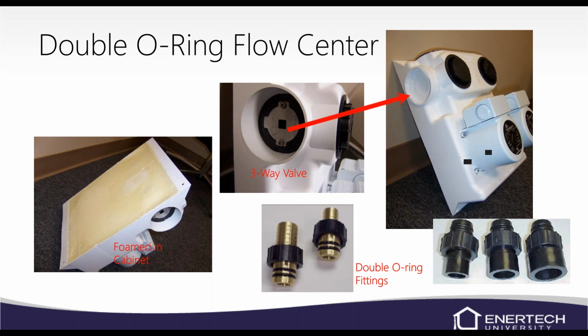And I just say, be real careful and double check to make sure that the seals are sealing properly and that they're in there straight. I've just seen a lot of flow centers come back, and they're leaking when they come back here. And it's normally on a brand new install.